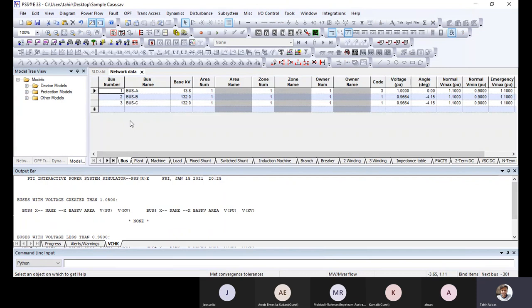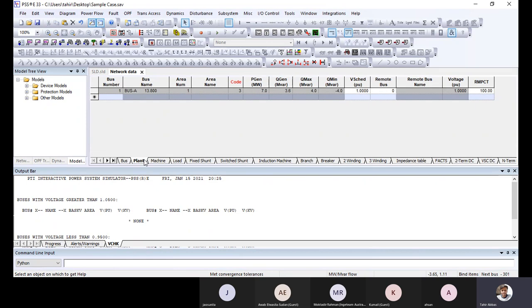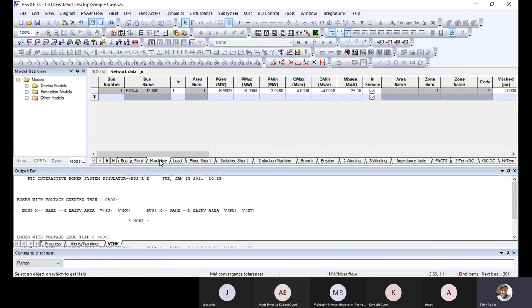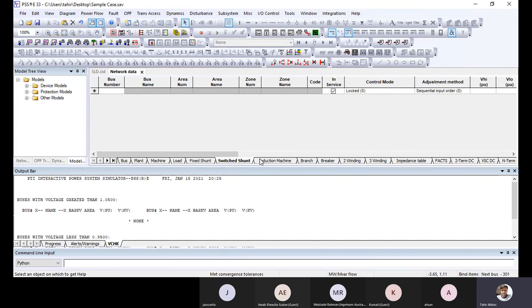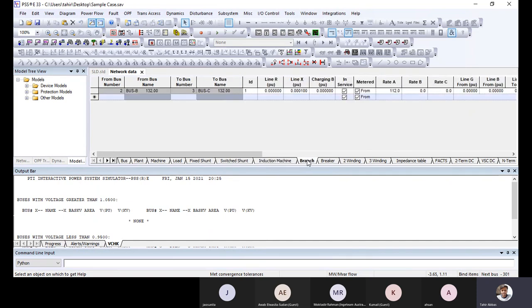Now coming back towards the network diagram, the network case, here you can see this is a bus and the plant tab, with only one plant and only one machine. Sometimes a plant has different machines, like in combined cycle plants, a steam turbine and a gas turbine. So there may be different machines also. And load data is here: fixed shunt, switch shunt, induction machine, branch data.